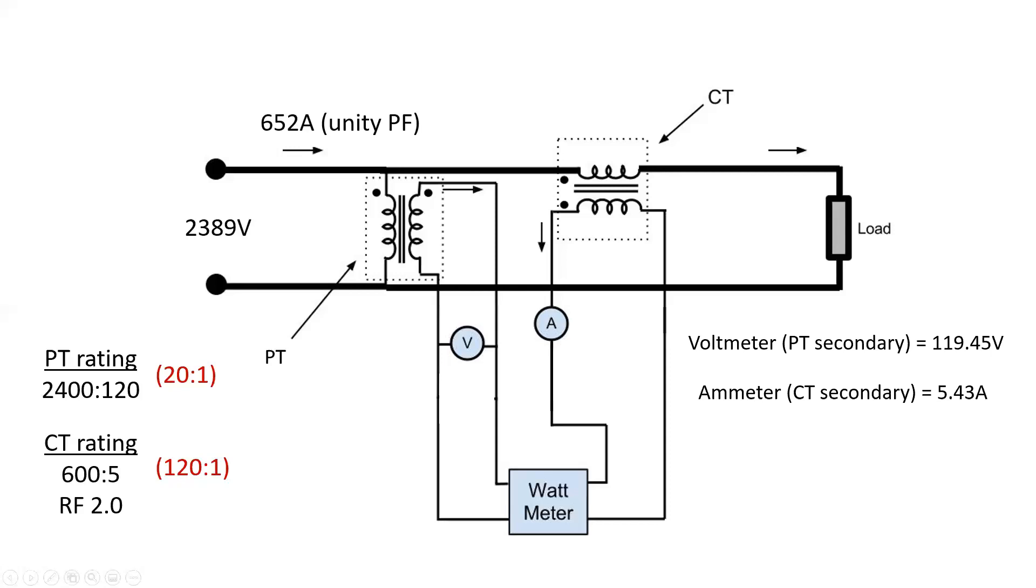So, if we take these two values together, if we were only given the voltmeter and the ammeter values and we knew what the ratios were of those two devices, the PT and CT, we could still work out what the total amount of watts was of the main system. And the way that we would do that is we would take 20, which is our PT ratio, times 119.45 volts and multiply it by 120, which is the ratio of our CT, and multiply it by 5.43, giving us 1.55 megawatts worth of power. Now, I understand why would you go through this process if you already knew 652 and 2389? And the answer is, we probably wouldn't. But remember, the only way we're going to be able to validate that there's 652 amps is through a CT that has a ratio. And the only way we can validate there's 2389 is through a PT and a PT ratio.